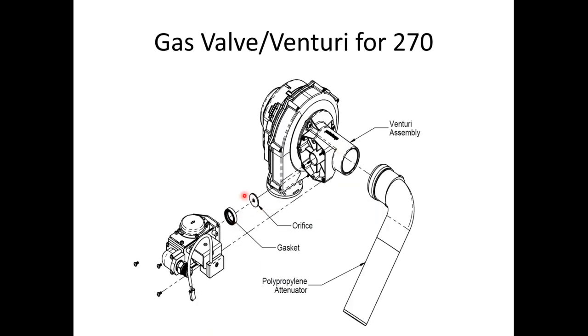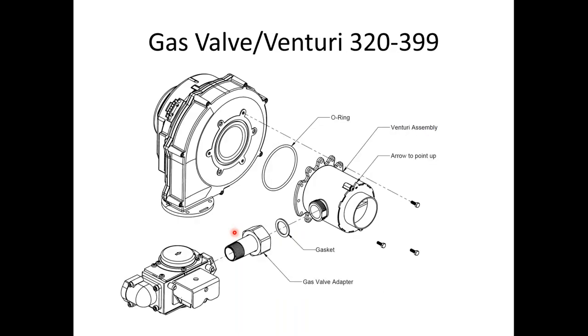The 270 is just the orifice. We'll pop it apart, pop it off the side, pop the orifice out of the gasket and pop it back in, and it's right back together. On the 320 and 399, the venturi looks similar to a small coffee can, or soda can. You are able to get it out without fully taking this apart. We undo this nut, and it'll give us enough space in here to pop this out.